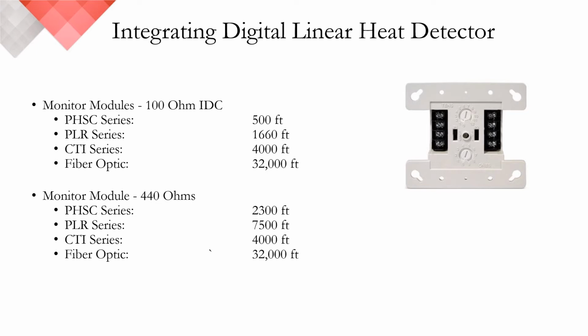Now, take into consideration that Protectowire conventional panels can support anywhere from 5,000 to 10,000 linear feet. You begin to see the challenges with presenting a viable solution with linear heat. And something of interesting note here, you'll notice that with CTI and fiber, these numbers do not change with the monitor module. This is due to the fact that each one of these series requires the interface module to be able to connect to the detector to properly function.